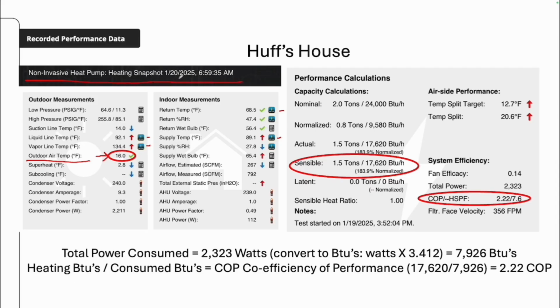And you can see right at the top here, non-invasive heat pump heating snapshot. It was taken January 20th, 2025 at 6:59 in the morning. Now, I did this before the sun came out because I wanted to see exactly what my system was doing, because I was trying to really determine my balance point in a real world application. Now, you can see here that my system is delivering 17,620 BTUs, and this is a 2-ton 17 SEER inverter driven heat pump. You can see my temperature split was 20.6.